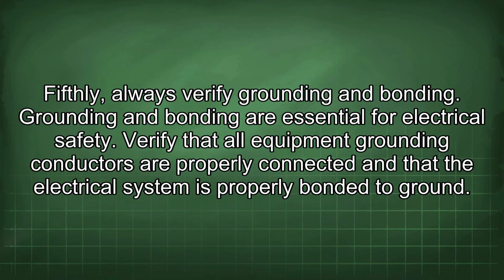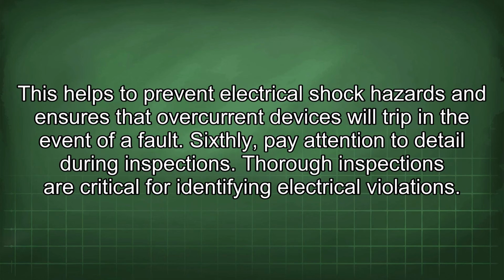Fifthly, always verify grounding and bonding. Grounding and bonding are essential for electrical safety. Verify that all equipment grounding conductors are properly connected and that the electrical system is properly bonded to ground. This helps to prevent electrical shock hazards and ensures that overcurrent devices will trip in the event of a fault.